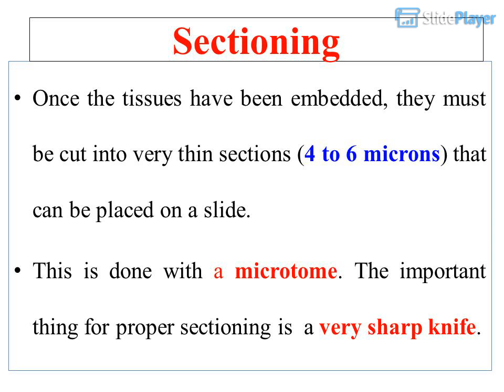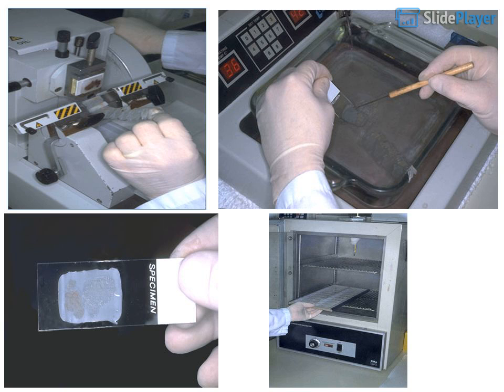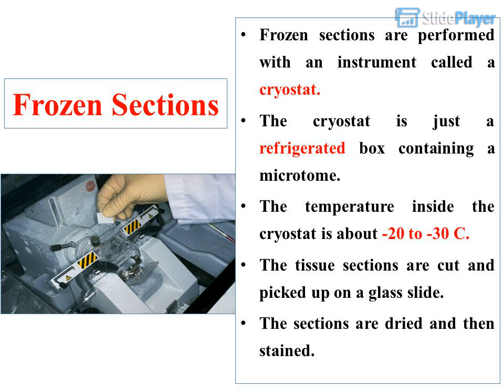Sectioning: Once the tissues have been embedded, they must be cut into very thin sections, 4 to 6 microns, that can be placed on a slide. This is done with a microtome. The important thing for proper sectioning is a very sharp knife. Frozen sections are performed with an instrument called a cryostat, which is a refrigerated box containing a microtome. The temperature inside the cryostat is about minus 20 to minus 30 degrees Celsius. The tissue sections are cut, picked up on a glass slide, dried, and then stained.